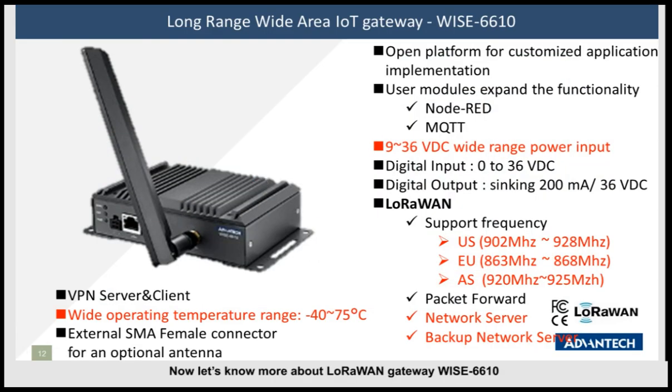Now let's look at more detail about the LoRaWAN gateway WISE-6610. As mentioned, it supports Node-RED and MQTT protocol, and features a wide-temperature range design. We have three frequency options supported: 915 MHz for the US, 868 MHz for the Europe region, and 923 MHz for Asia. WISE-6610 also embeds a network server. When data is collected from nodes and delivered to the gateway, it is decrypted via the embedded network server, keeping data with high security.